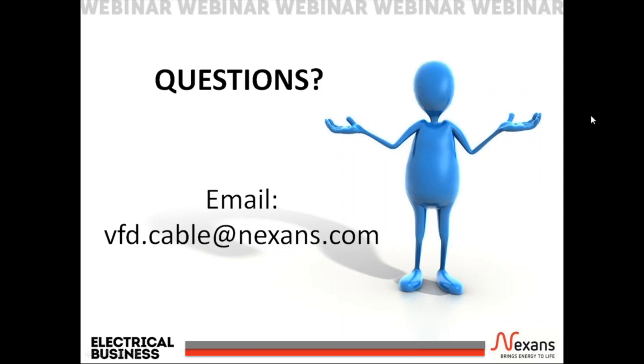in their manuals. Again, going back to that earlier slide on installation tips, those drive manufacturers are the experts with their drives. If they demand, if they suggest using line and load reactors, then do it. I think it's pretty clear. They will help, but no matter what type of filtering you add, you won't remove the need for a VFD cable. That's really what it comes down to.